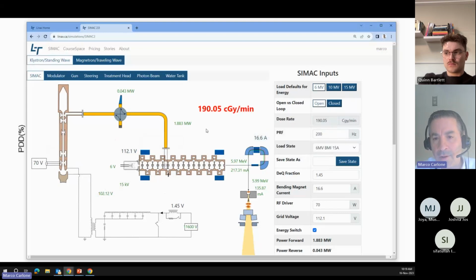And this leads to a beam energy of about 6 MV exiting the accelerator, and then about 6 MV striking the target. The two aren't necessarily the same, depending on how you configure the machine, and I'll talk about that in a second.